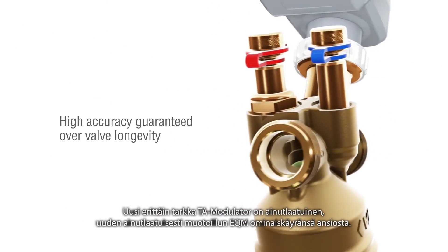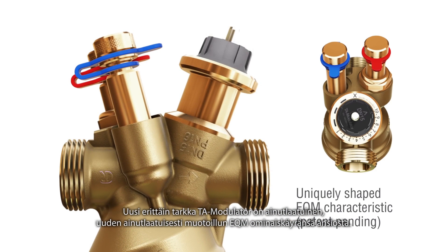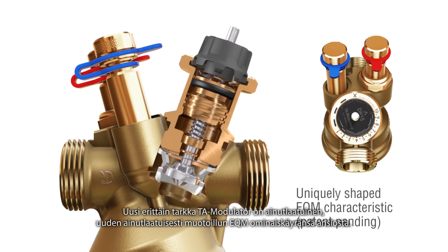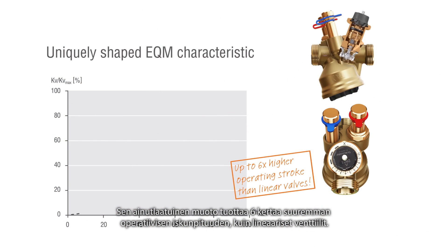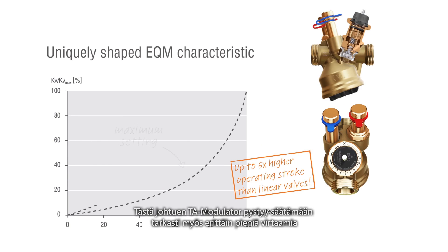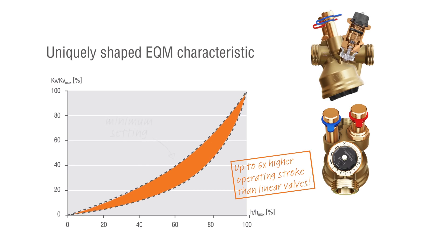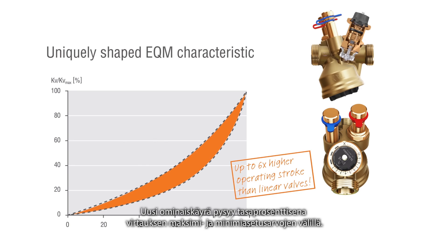The new highly precise TA modulator is unique due to its new patent-pending uniquely shaped EQM characteristic. Its uniquely shaped profile provides an up to six times higher operating stroke than linear valves. Therefore, TA modulator is able to precisely control also very small flows. The new characteristic remains equal percentage within the range of maximum and minimum flow settings.